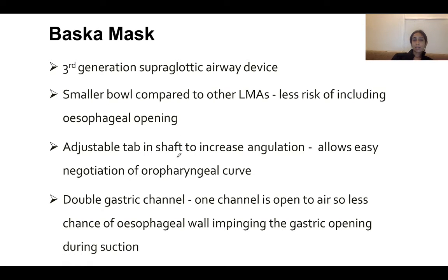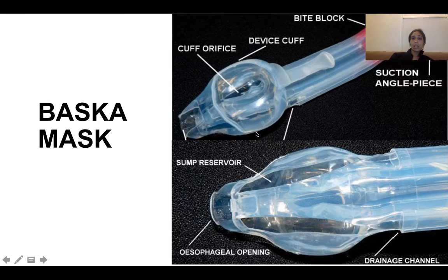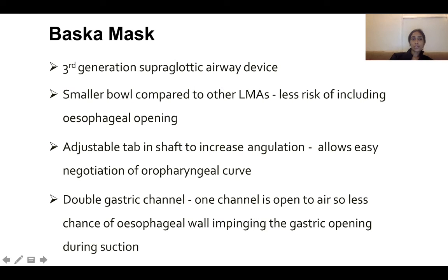It has an adjustable tab in the shaft to increase angulation, so it has a tab over here which allows easy negotiation of the oropharyngeal curve. It has a double gastric channel. One channel is open to air, so there is less chance of the esophageal wall impinging on the gastric opening during suctioning. Because of the suction pressure, and because it allows air, there's less chance of it impinging.